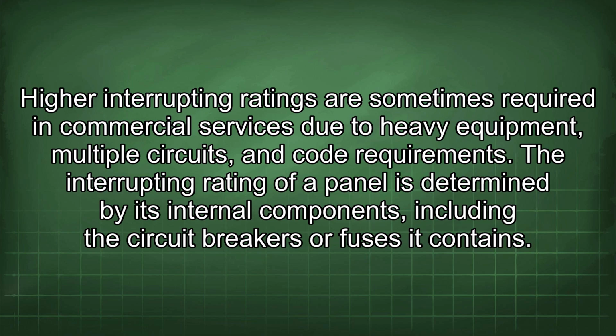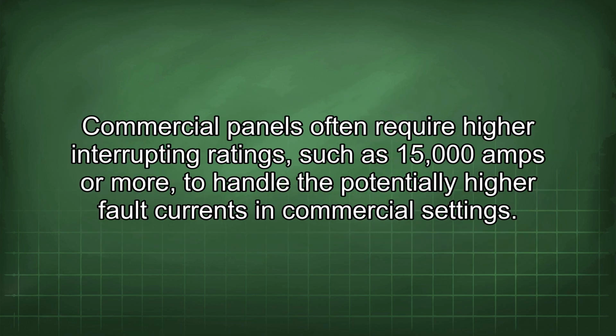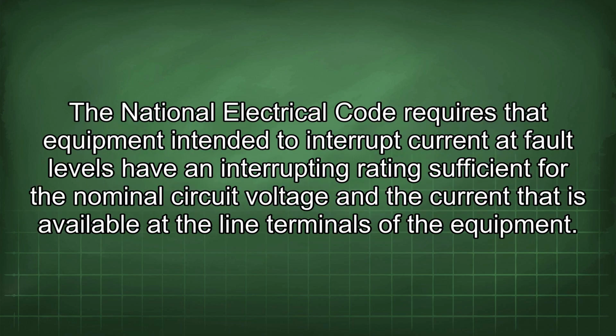The interrupting rating of a panel is determined by its internal components, including the circuit breakers or fuses it contains. Commercial panels often require higher interrupting ratings, such as 15,000 amps or more, to handle the potentially higher fault currents in commercial settings. The National Electrical Code requires that equipment intended to interrupt current at fault levels have an interrupting rating sufficient for the nominal circuit voltage and the current that is available at the line terminals of the equipment.